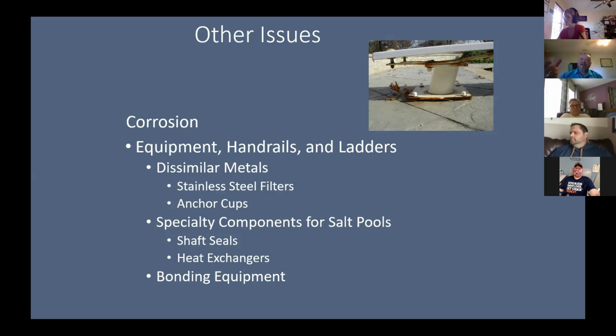So where does the splash-out water become corrosive? When the water starts evaporating. In the pool, we're at 3,000 parts per million, which is not corrosive. You take that water and splash it out onto the deck or onto something metallic. As the water evaporates, that 3,000 parts per million of salt becomes 5,000, 6,000, 8,000, and the concentration increases, and that's where it becomes more corrosive. Corrosion on equipment, handrails, and ladders: dissimilar metals, such as stainless steel filters, or brass anchor cups with stainless steel handrails, can cause corrosion just by themselves, not as a result of salt systems.